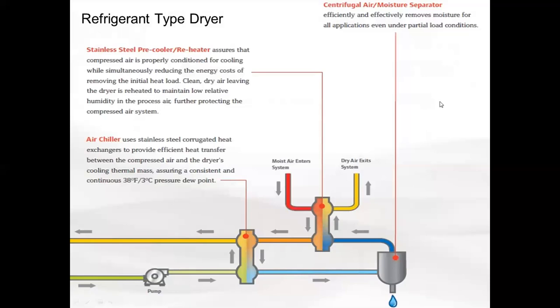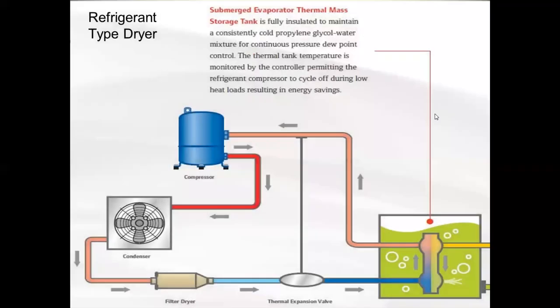So it's good to uncouple these, because if I go back up here, we may not be drying much air, in which case we're not heating this glycol up very quickly, which means this compressor doesn't need to run very much. And so when you decouple these things, the refrigeration system maintains this temperature, and then we take that cold glycol off to another heat exchanger in order to do the cooling of the air and the removal of the moisture. It saves energy. In the older systems, this thing operates all the time, and you don't have this thermal mass involved. So this costs a little more on the front end, but is a whole lot more efficient.